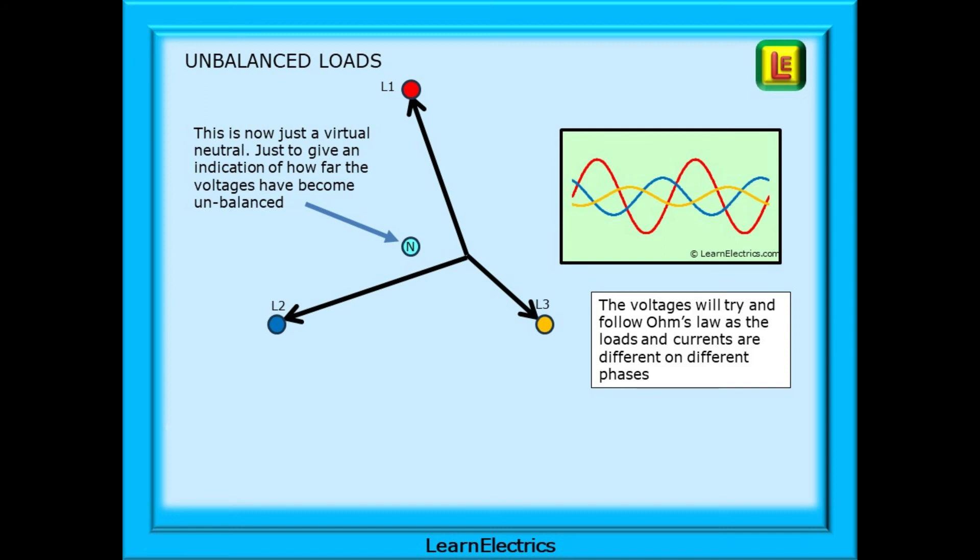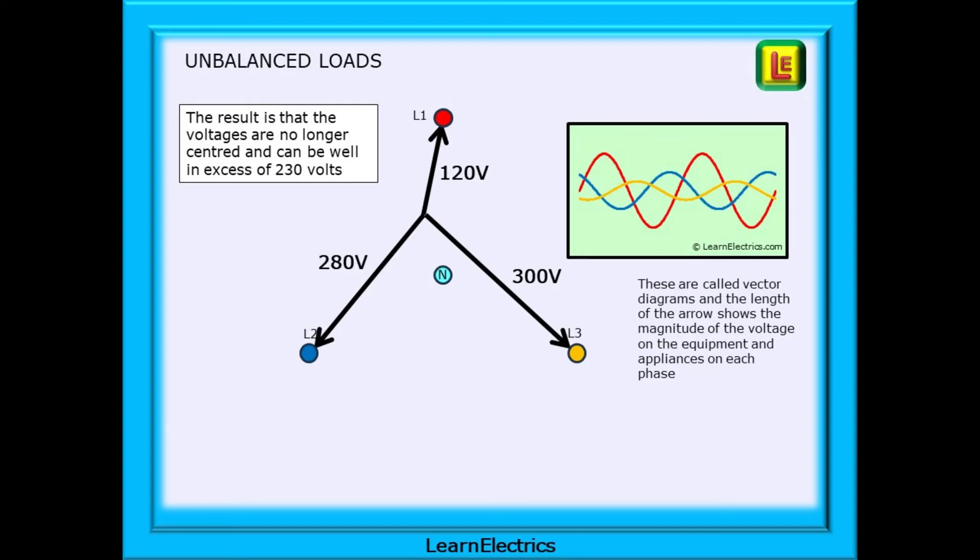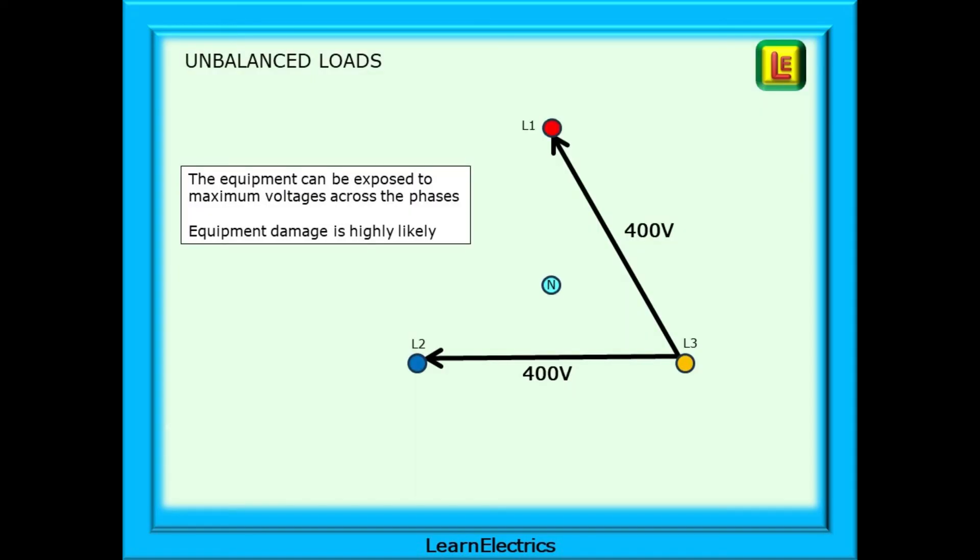An unbalanced load is very different. There will be varying loads on each circuit. As the loads vary and as the current demands vary, the voltages will try and follow Ohm's law to match the loads and currents on different phases. The neutral point has been left on the drawings as a reference for you, to show how the voltages have moved away from a balanced 230 volt state. The result, as you can see, is that the voltages are no longer centered and can be well in excess of 230 volts. These are called vector diagrams and the length of the arrow shows the magnitude of the voltage on the equipment and appliances that are on each phase. The equipment can be exposed to maximum voltages across the phases, as shown here, where the vectors are at their maximum length. At this point, equipment damage is highly likely, almost inevitable, as equipment overheats with the risk of fire.